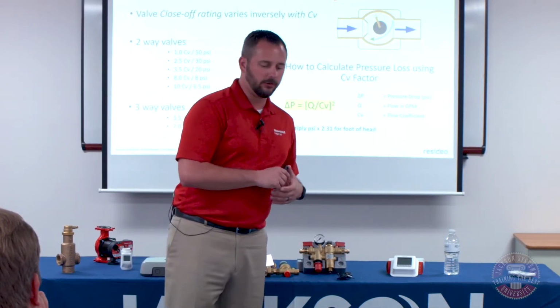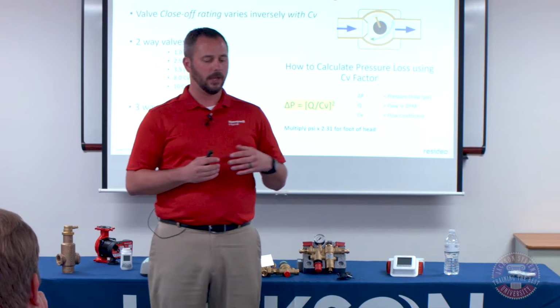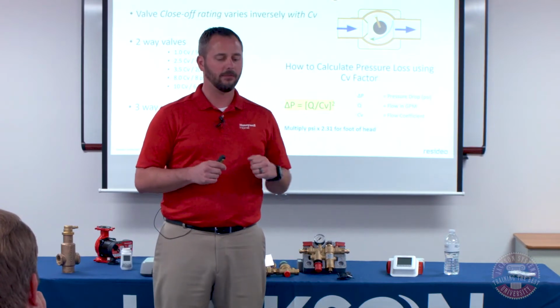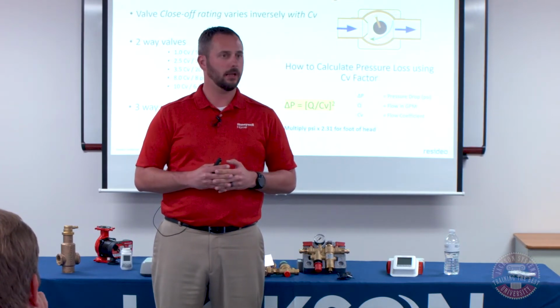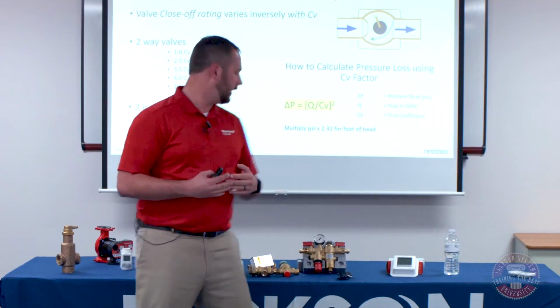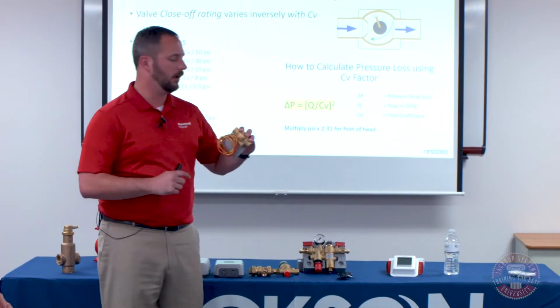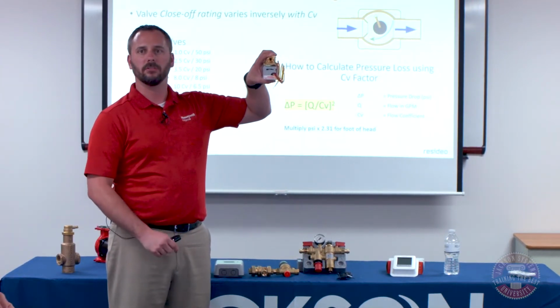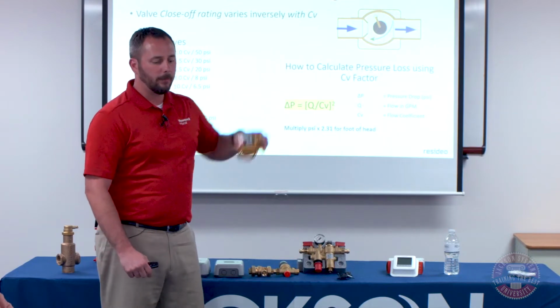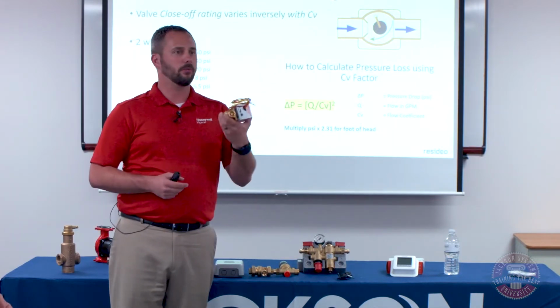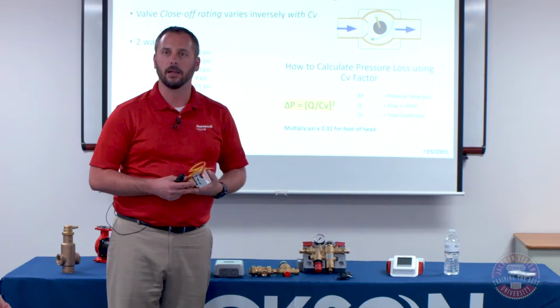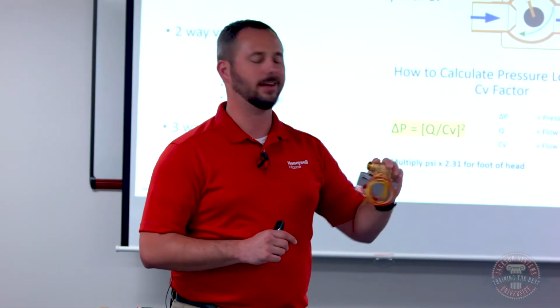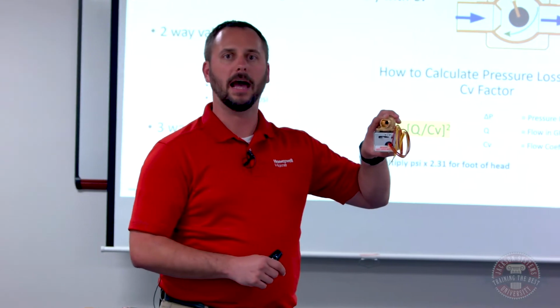So when we look at this in a 3/4 zone valve, my number's not up here, but we have a 3.5 CV rating, which is one of the most common. I think that's actually the one I have in my hand. It looks like it's got a little bit of resistance on there, and that's true. But we also make a zone valve in a 3/4 inch that has a 6 CV rating. The 6 CV rating looks almost like it's a full port. It's technically not, but it's much more open than the passageway through that one.